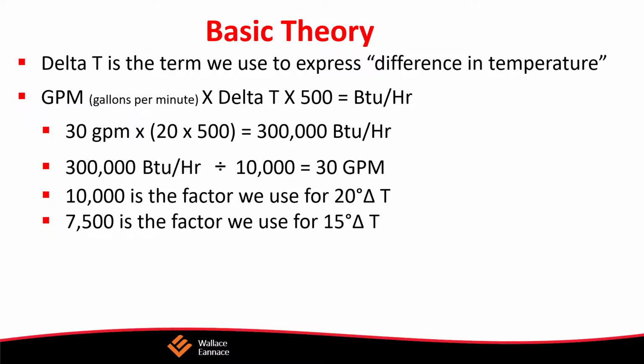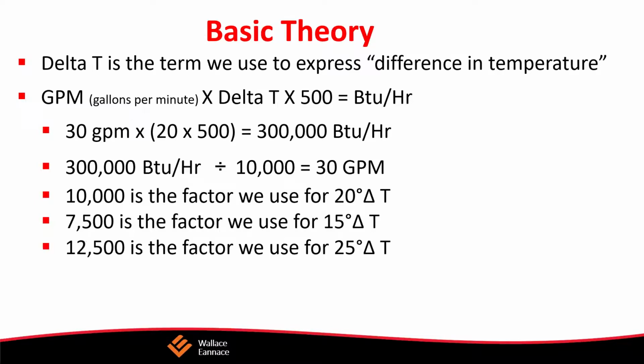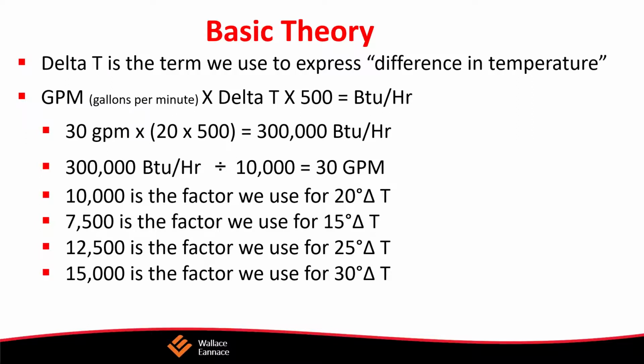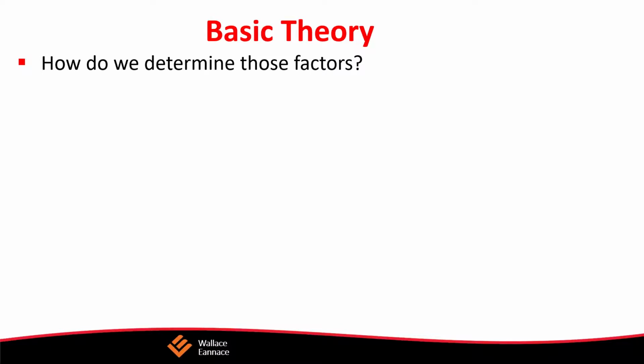So 10,000 is the factor that we use for 20-degree delta T. If we had 15-degree delta T, we'd use 7,500. If we had 25-degree delta T, it'd be 12,500. And then for 30-degree delta T, it would be 15,000. The key thing is that most hydronic systems, we design traditionally for about 20-degree delta T. So therefore, we tend to use the 10,000 number all the time.